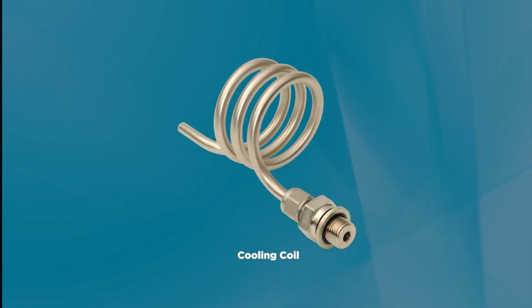The stainless steel construction of the coil and its length typically provide enough heat transfer to cool the gas to acceptable temperatures. The other, less obvious use for the cooling coil is as a venting coil on the sample cell outlet, in which case the coil serves to prevent ambient humidity from backflowing into the sample cell when the pressure entering the sample cell is either low or atmospheric.